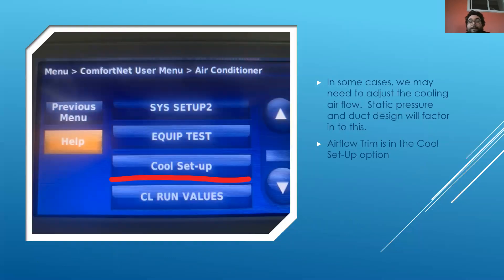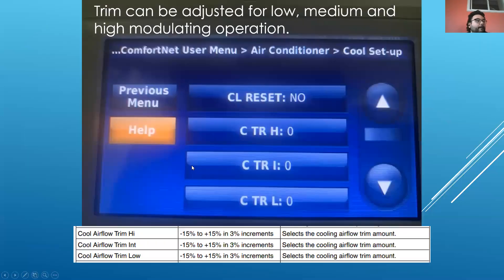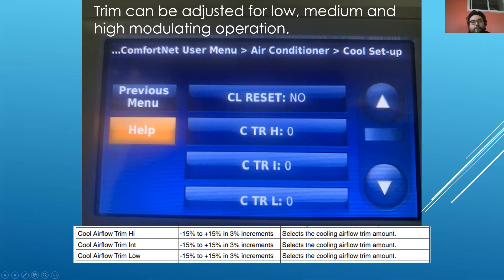In some cases you may need to adjust the airflow. Duct design and static pressure restrictions will really factor into how the fan is operating. To change that, go into the Comfort Net user menu under air conditioner and select cool setup. In there you have the option of adjusting trim on the lowest modulation, the middle ground, and the highest modulation. You can go from negative 15% to positive 15% in 3% increments — select each one as needed.